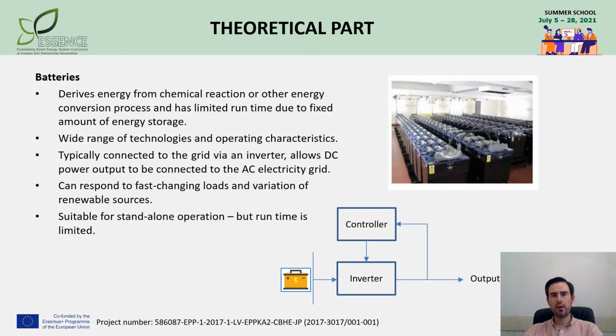The batteries may help to balance fast-changing loads and variable sources of a microgrid, thus allowing standalone operation. However, the runtime is limited due to their limited capacity, and due to the relatively high costs, the expediency of the application shall be confirmed by a feasibility study.